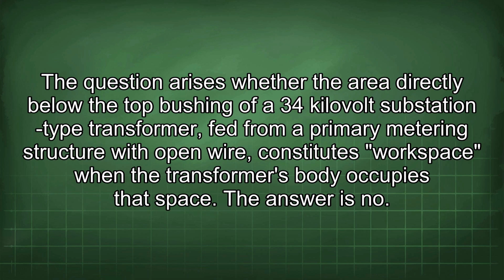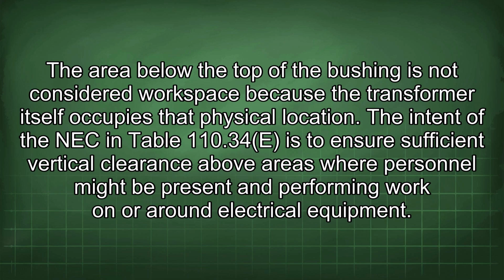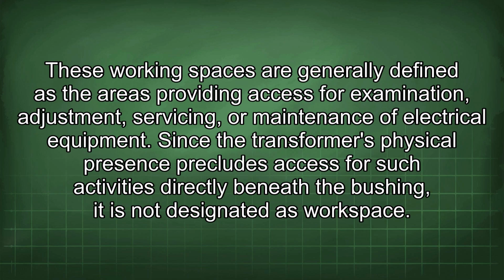The answer is no. The area below the top of the bushing is not considered workspace because the transformer itself occupies that physical location. The intent of the NEC in Table 110.34(E) is to ensure sufficient vertical clearance above areas where personnel might be present and performing work on or around electrical equipment. These working spaces are generally defined as the areas providing access for examination, adjustment, servicing, or maintenance of electrical equipment. Since the transformer's physical presence precludes access for such activities directly beneath the bushing, it is not designated as workspace.